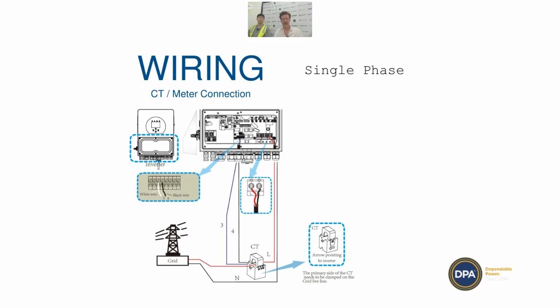You can see we've got the inputs for the CT here in the diagram, and so it's just these push-in style connectors, the third and the fourth on this particular model. What's really easy to do is to get the CT the wrong way around, and that goes for when you're using the meter as well.